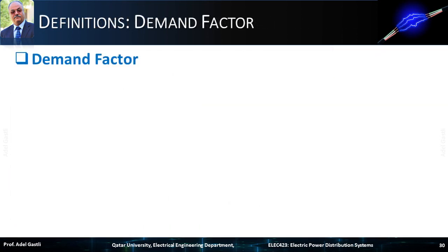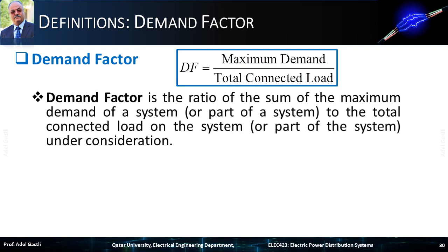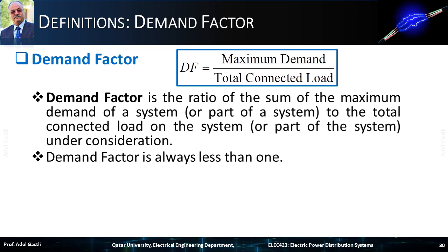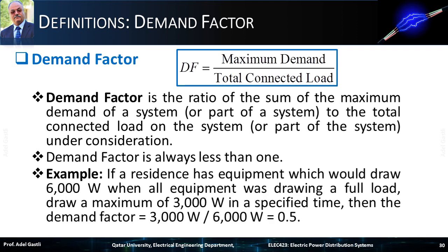Now we will define the demand factor. The demand factor is the ratio of the sum of the maximum demand of a system, or part of a system, to the total connected load on the system under consideration. So the demand factor is always less than 1. For example, if a residence has equipment which would draw 6,000 watts when all equipment was at full load, and draws a maximum of 3,000 watts in a specified time, then the demand factor equals 3,000 over 6,000, which equals 0.5.